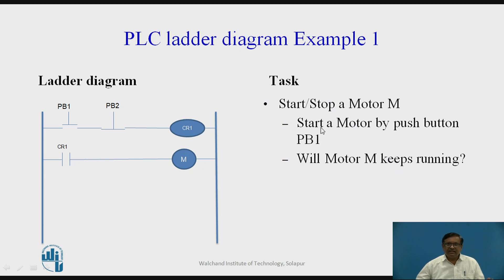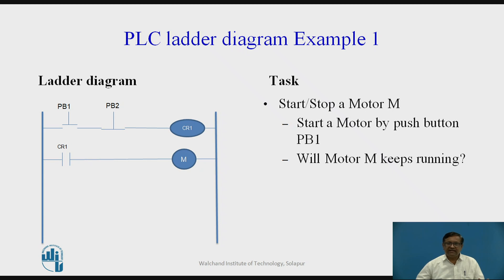Since PB1 is a push button, if you remove your finger from it, the contact opens, CR1 de-energizes, its contact opens again, and the motor stops. So the question is: will motor M keep running? No, because as soon as you release the push button, the motor gets stopped. So how can we modify this ladder diagram so that I can start the motor with one button and keep it running until stopped by another button? That is what example 2 will discuss.